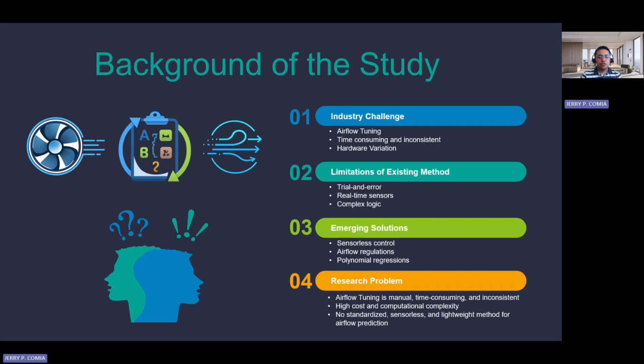Airflow tuning is important in systems such as fans, blowers, and ventilation units because these systems need to maintain specific airflow levels during operation. However, in many production environments, airflow tuning is still done manually. This makes the process time-consuming, inconsistent, and affected by hardware variations between units. Existing methods may use trial and error, real-time sensors, or complex control logic. While these methods can work, they may increase cost, calibration time, and computational complexity.